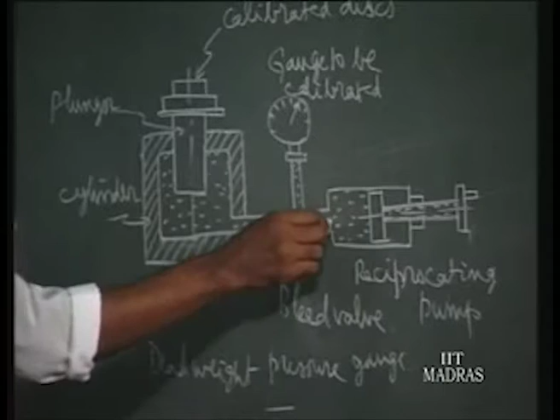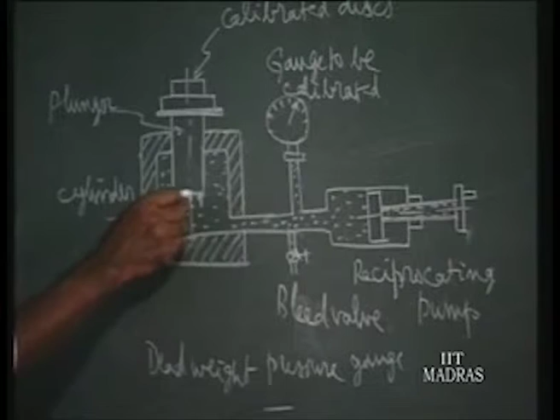For fine adjustment, we can use this bleed valve to take away a little liquid so that fine adjustment can be made. When there is no pressure developed, the plunger will sit at the bottom, and when you rotate this, the pressure builds up. Before adding the calibrated disc, only the dead weight alone will be there. By rotating we can make this float, when the pressure developed in the liquid into the area of the plunger is equal to the weight of this plunger, then it starts floating.